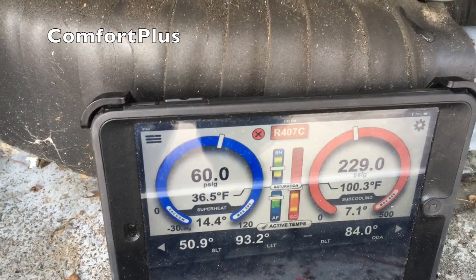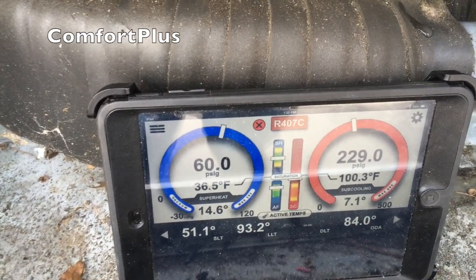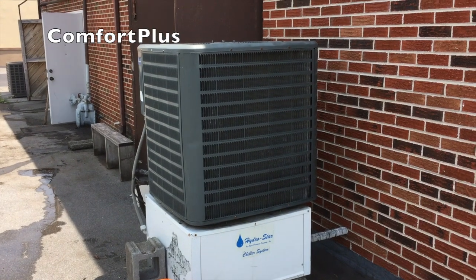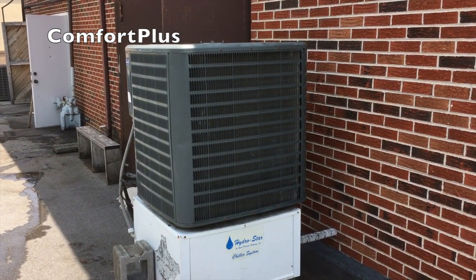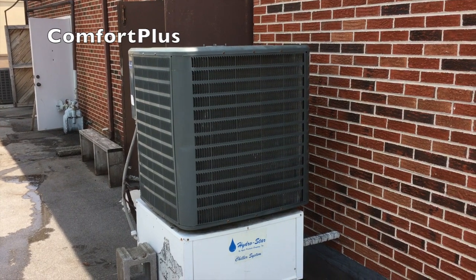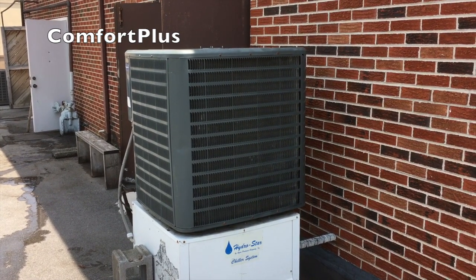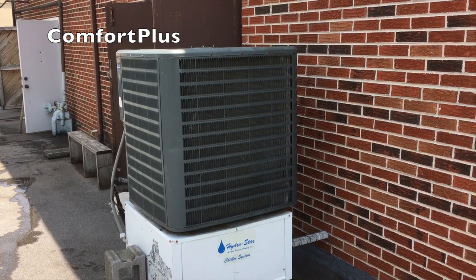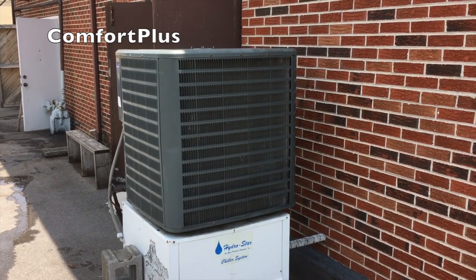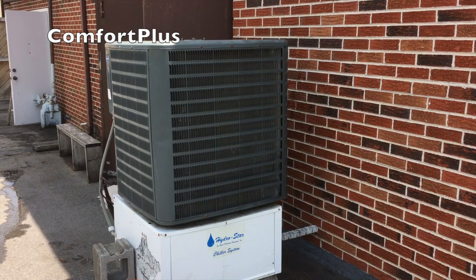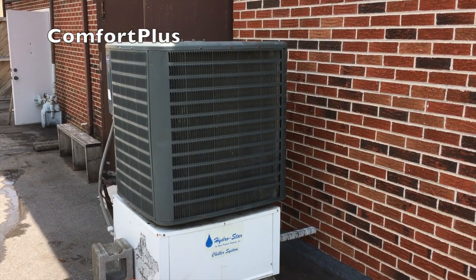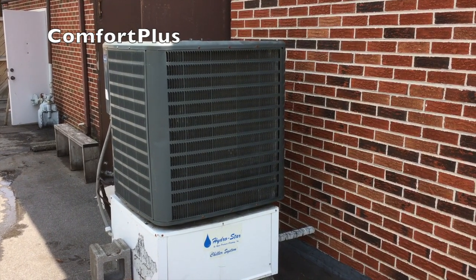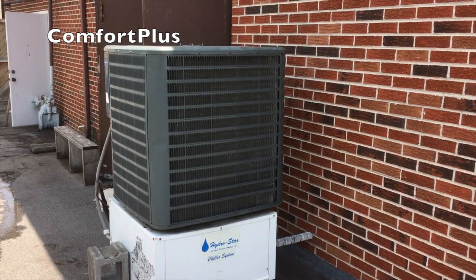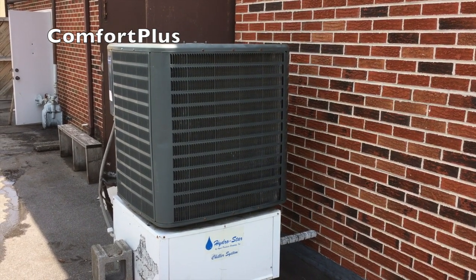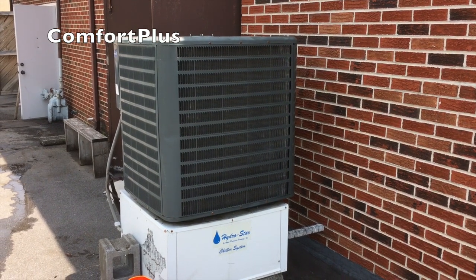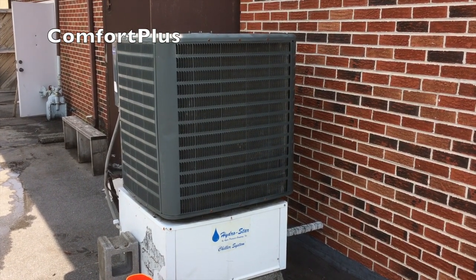So I'm going to leave her set right there and start buttoning it up. All done. We wound up raising the set point from 50 to 55 degrees because it was doing a lot better job of keeping the water cool when the system was running inside. He called the manufacturer of the indoor equipment and they told him what the inlet and outlet temperature should be, and we got it set up for that. So I guess the old compressor, because it was dragging, had reduced capacity. Of course, we added a little bit of capacity, but still I don't think we added that much.